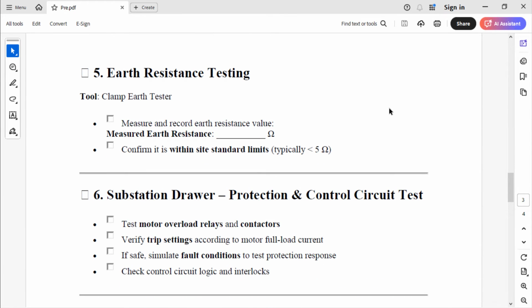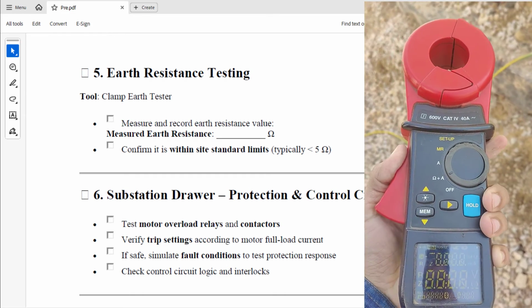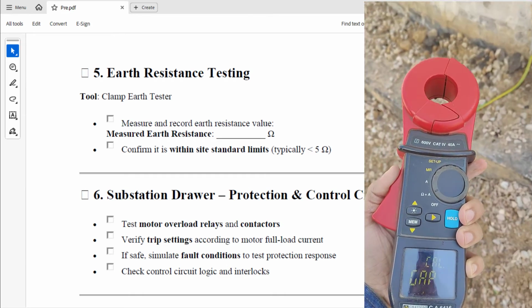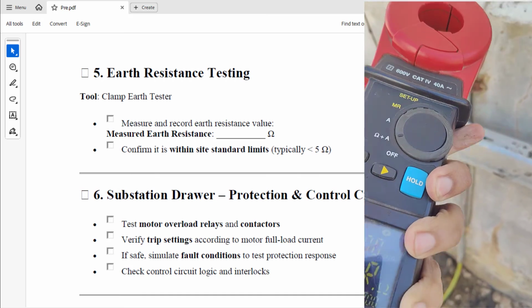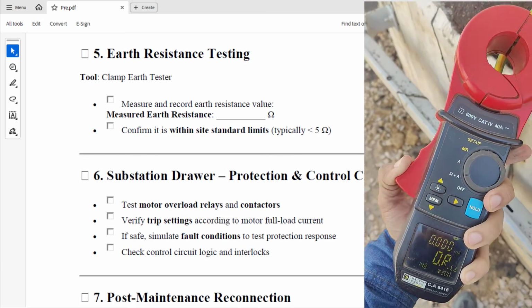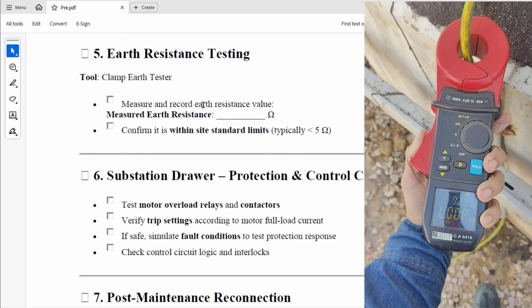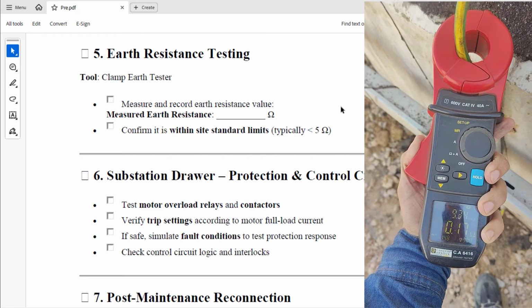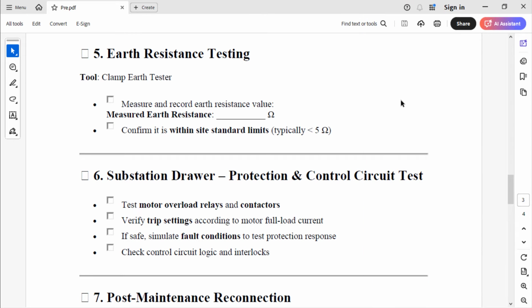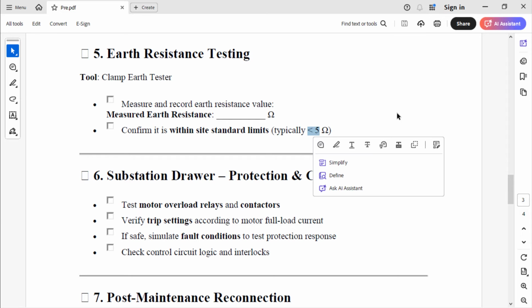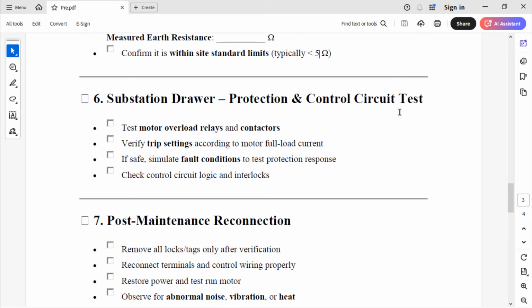Now let's record the values and compare them with the fingerprint value, the reference values we have in our logbook. Now let's bring a clamp earth tester and measure the resistance of earthing. Measure and record the earth resistance value and confirm it is within site standard limits. Typically, it's less than 5 ohm. Sometimes it's less than 2 ohm.